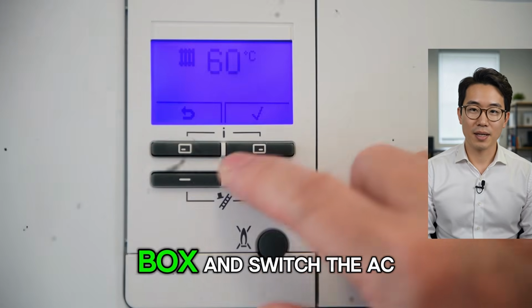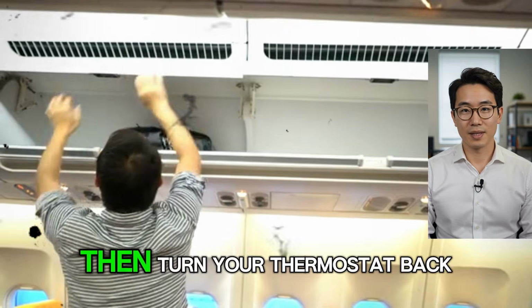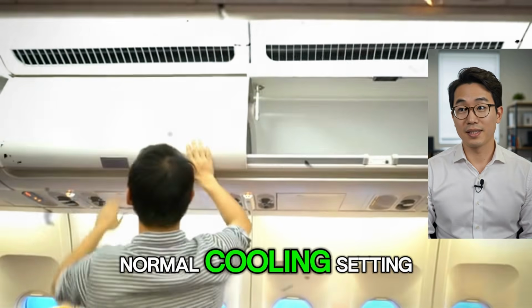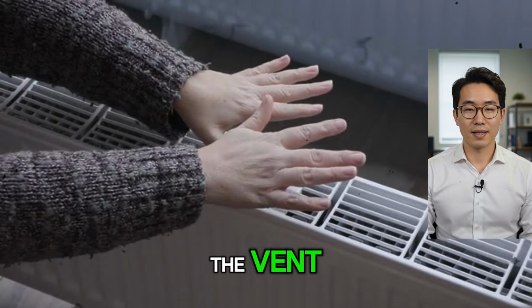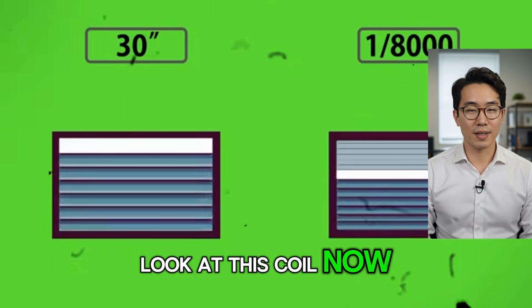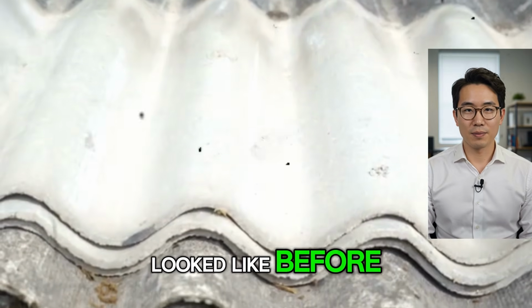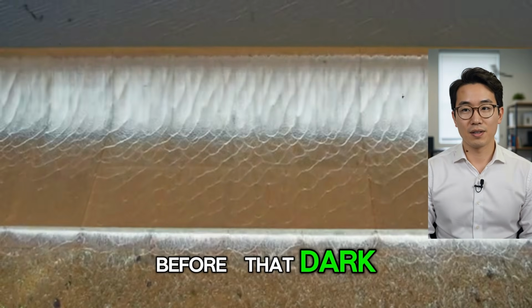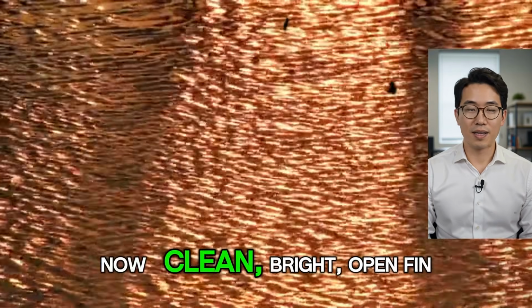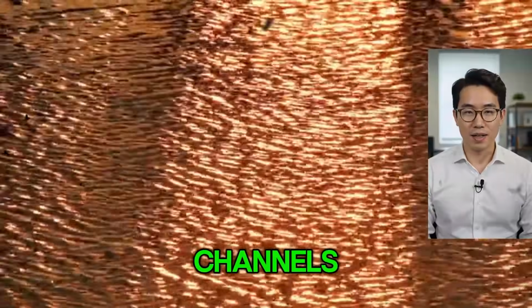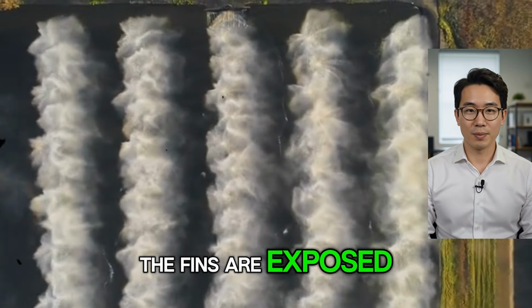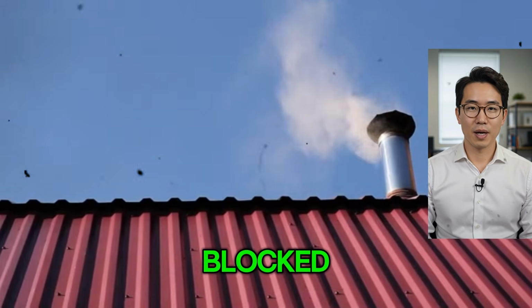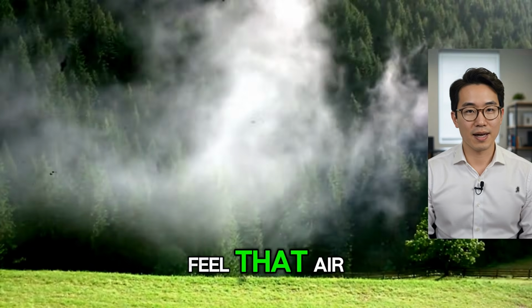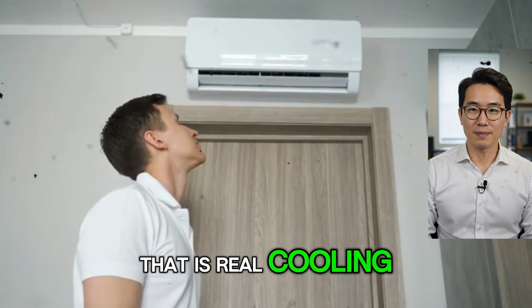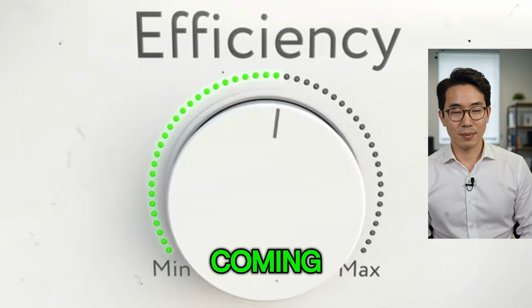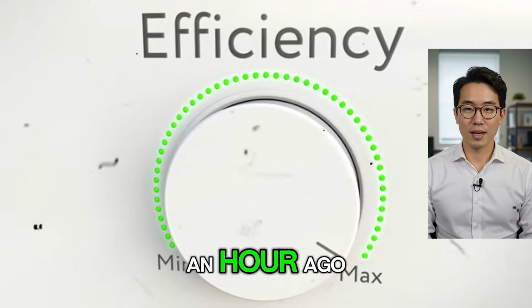Go back to your breaker box and switch the AC breaker back on, then turn your thermostat back to your normal cooling setting. Now stand in front of the vent and wait. Look at this coil now. Compare it to what it looked like before. Before, that dark, clogged, matted surface. Now clean, bright, open fin channels. You can see the metal again. The fins are exposed. The airflow is no longer blocked. Feel that. Feel that air. That is real cooling. That is cold, efficient air coming from a unit that was barely functioning an hour ago.